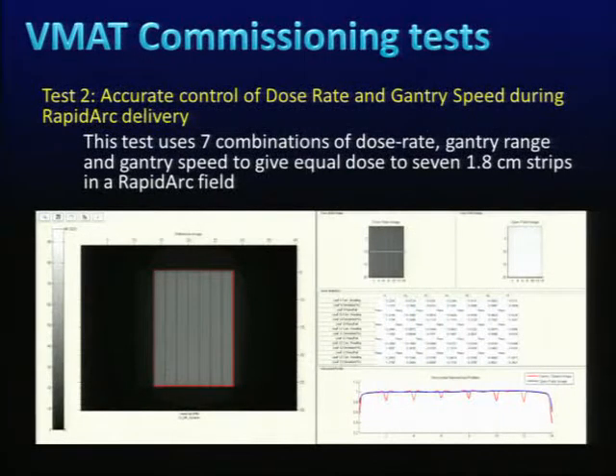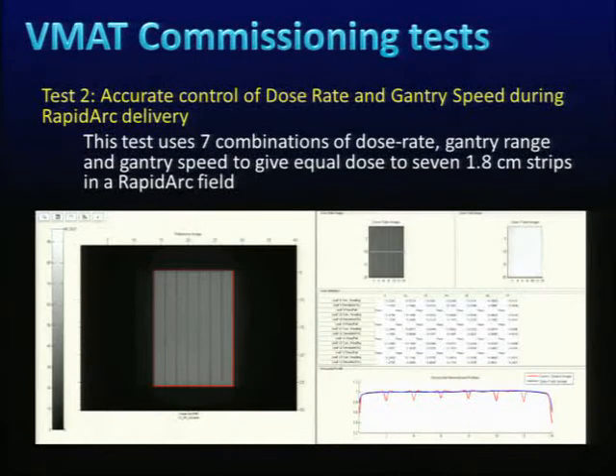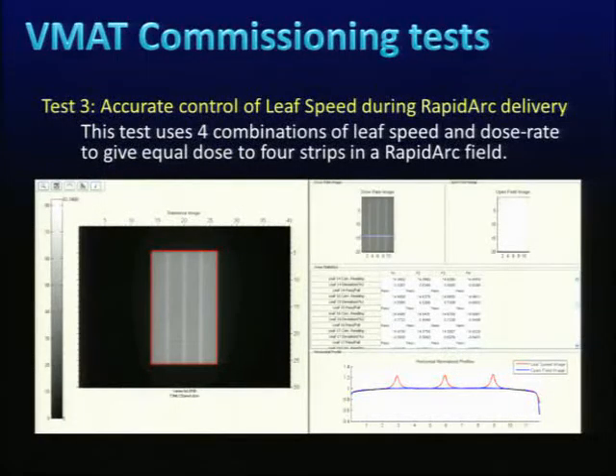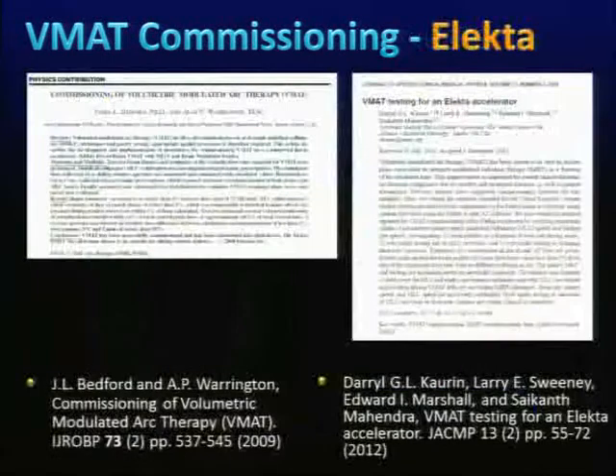The next test involves seven combinations of dose rate and gantry speed. Seven strips are normalized to the open field — the blue represents the open field and the red profile shows the seven combinations. Our tolerance was 2%, and all seven combinations passed. Similarly, for leaf speed combined with dose rate changes, four combinations were compared to the open field and passed within 2%.